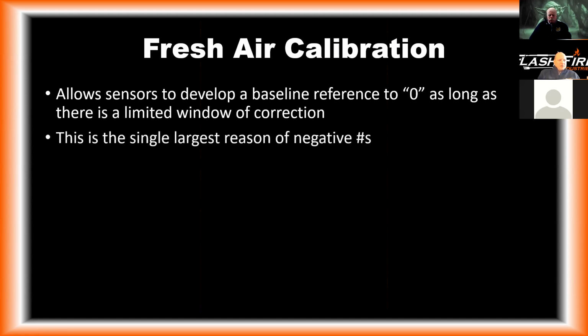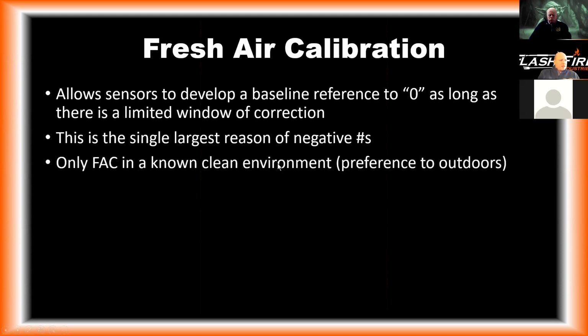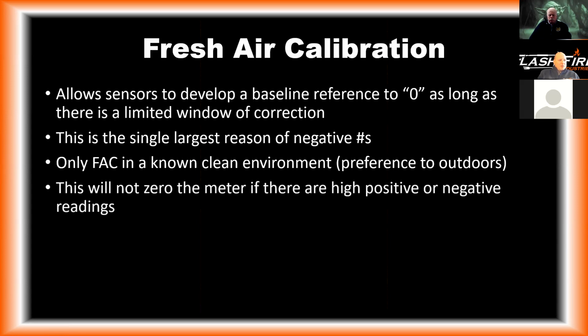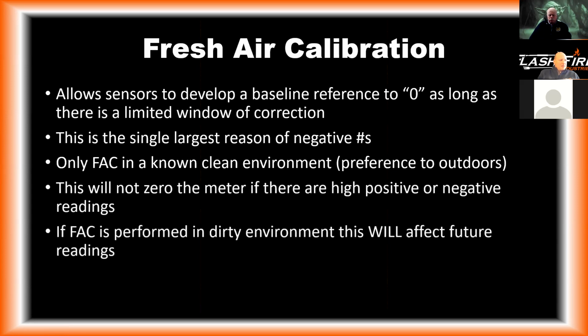This is the single largest reason for negative numbers. As we get further away from when we calibrated the meter last, we're going to start to get some drift on the sensors. Fresh air calibration should bring us back to 0. We only want a fresh air cal in a clean environment. Again, preference to being outdoors away from the exhaust of the apparatus. It won't zero if we're at high negative or positive readings. If fresh air cal is performed in dirty environments, then this can and will affect our future readings.